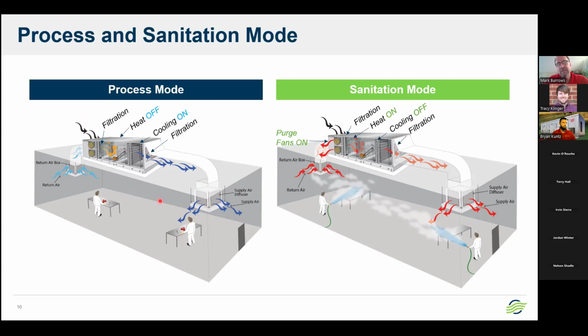What is directly downstream of the cooling coil is the filtration scenario. Those filters like to run about 550 to no more than 600 feet per minute as well. So think in terms of your cooling coil and your filters at or about the same velocity going through them. We showed a photograph before of a unit that had some filters missing. What happens when you take the static pressure away from the filters? It's about a 0.25-inch water column on a pre-filter, which is the 2-inch throwaway. It's as much as 0.75 to maybe 1 inch on a final filter.